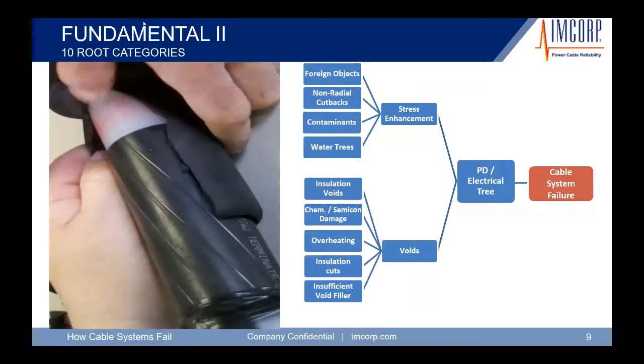So, improper installation of void filler. This is another common issue. Some of the instruction sheets that we see will require you, and if you can see there's this red material, that's a void filler by one of the manufacturers that has to set right next to the semicon material. There's a difference in diameter between the semicon and the insulation. So that step down right there can leave a void, an air pocket, where energy is ionized at a high level, like 10 times the voltage, and it begins to break down that insulation. So the components, again, are not put on properly.